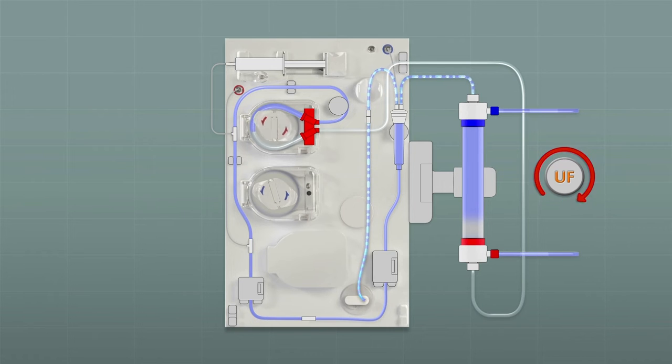Air is removed from the dialyser and the bloodline so the LX automatically changes the blood pump speed and uses the venous clamp to remove air bubbles from the dialyser.